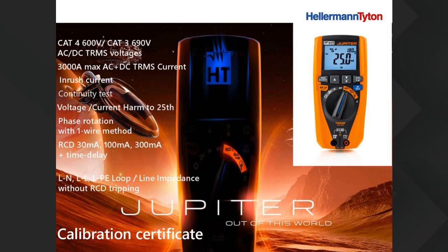Now, this is very, very new in the market, where normally when you do phase rotation, you've got a meter that's got 3 crock clips that you need to make contact with the metal. A lot of times it's very difficult to make contact with the screws or the wires and so on. And this meter makes it so much easier, where you use only one wire and you can physically go from phase 1 to phase 2. The meter memorizes phase 1 to phase 2 and then calculates the phase rotation on that system.